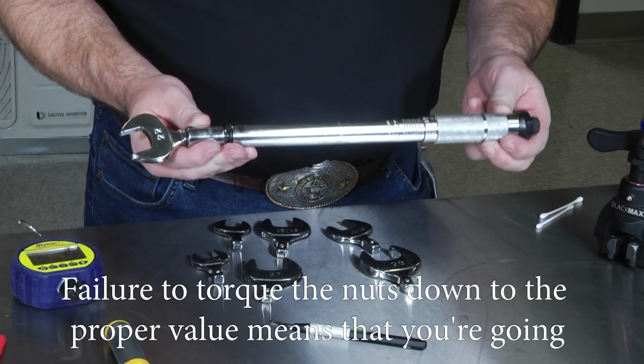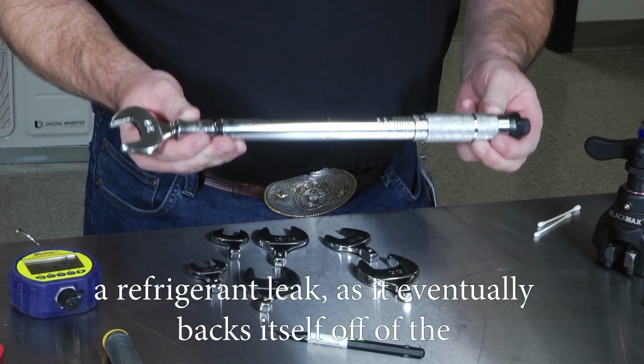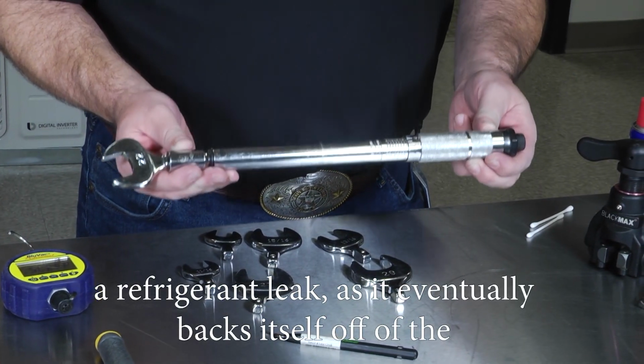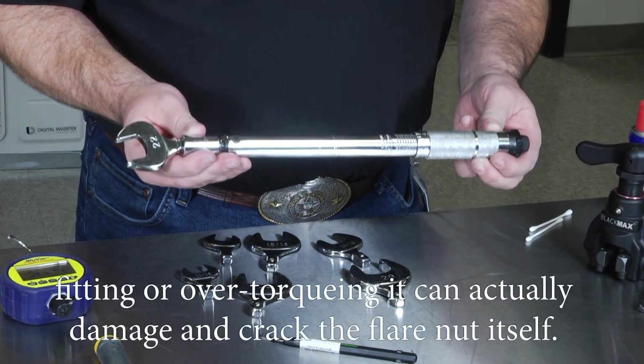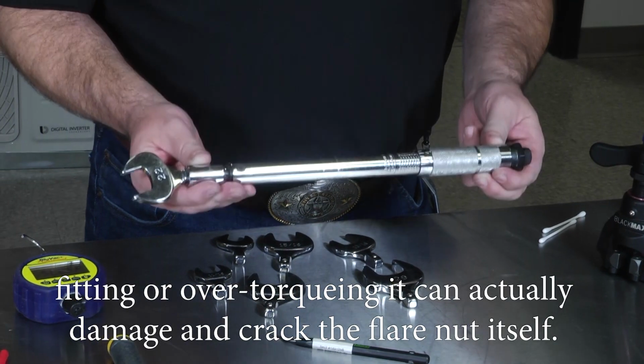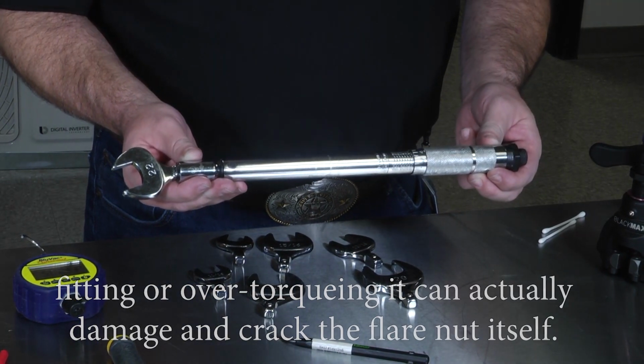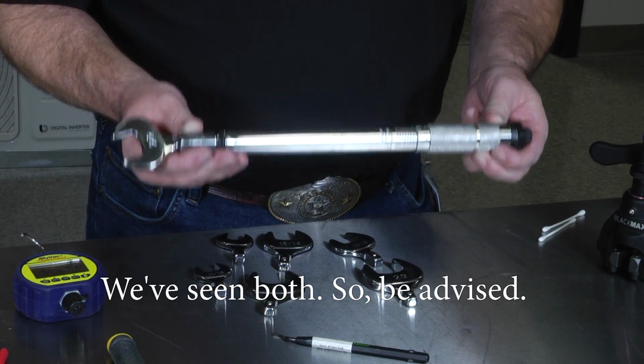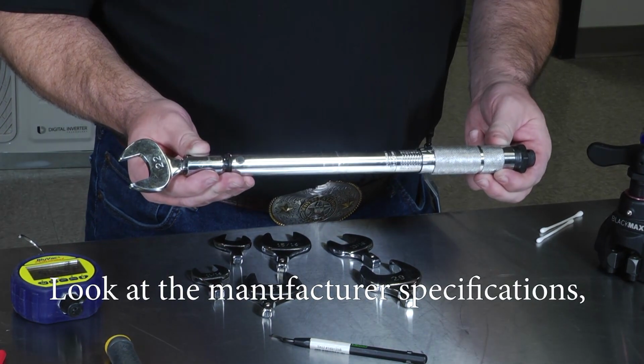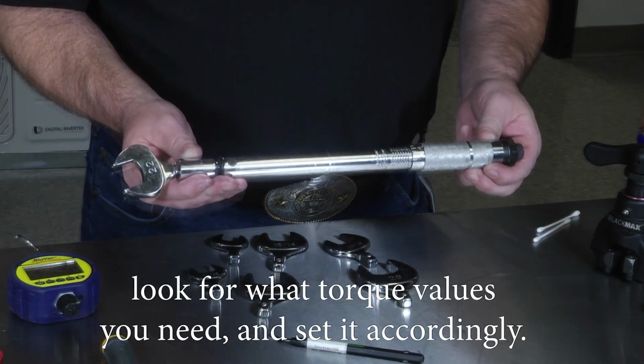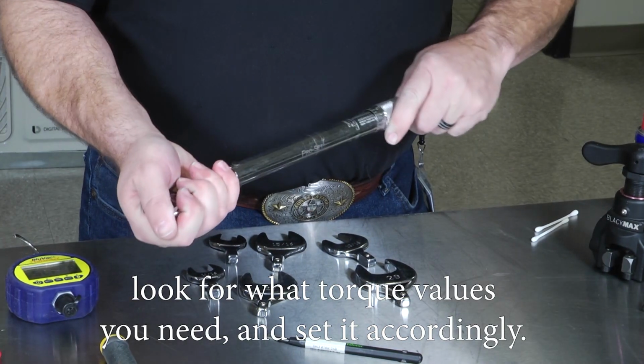Failure to torque the nuts down to the proper value means you're going to have a refrigerant leak as it eventually backs itself off of the fitting, or over torquing it can actually damage and crack the flare nut itself. We've seen both. So be advised, look at the manufacturer specifications, look for what torque values you need, and set it accordingly.